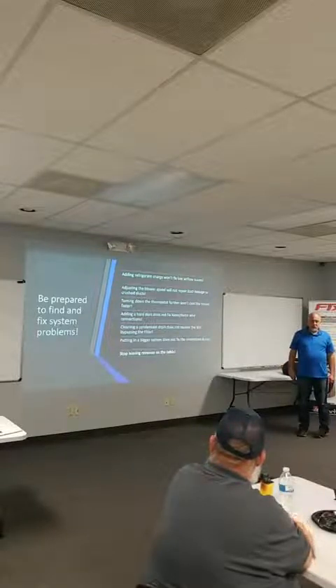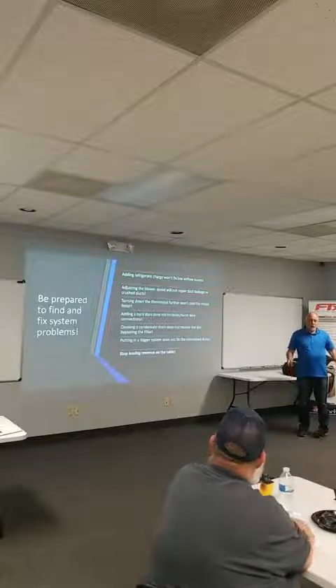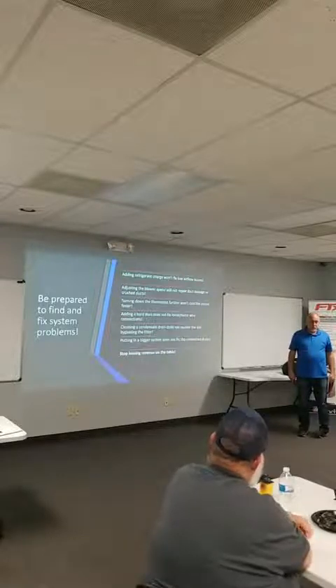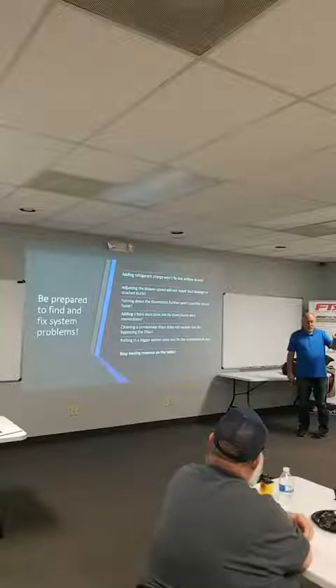It's like, did you take a look at the wiring, right? That's a big pet peeve of mine. Every couple of years, you need to pull the panel off the system. And you need to shut off the breaker first. You need to check and see if the connections in the breaker are tight, right? Because the connections loosen up, because things get hot. Every time it starts, it pulls a lot of current. It loosens up the screws on the breaker.